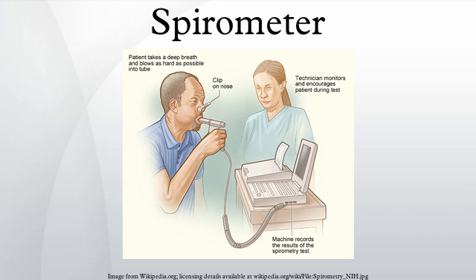The Incentive Spirometer is specially designed to improve one's functioning of the lungs. The Peak Flow Meter is useful for measuring the ability of a person to breathe out air. The Windmill Type Spirometer is used specially for measuring forced vital capacity without using water, with measurements ranging from 1,000 millilitres to 7,000 millilitres. It is more portable and lighter compared to the traditional water tank type spirometer, and should be held horizontally while taking measurements due to its rotating disk.